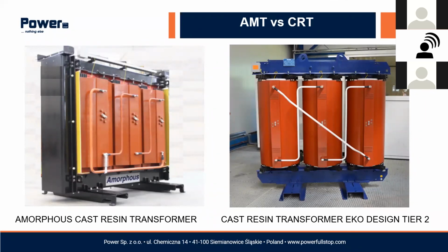On the left side, you see a typical amorphous execution. As you see, it's a totally different design. The windings are not round, they are more squared, and there is a special structure fixing the amorphous transformer around. Why? The core, which is produced here, is made in a totally different way than the traditional grain-oriented core. The material is also totally different.